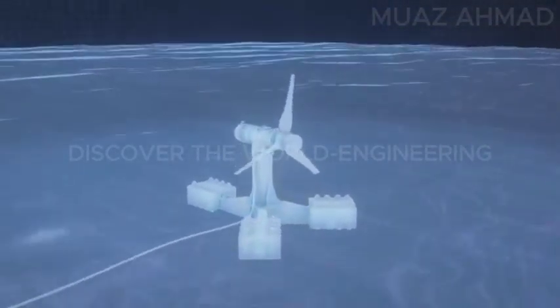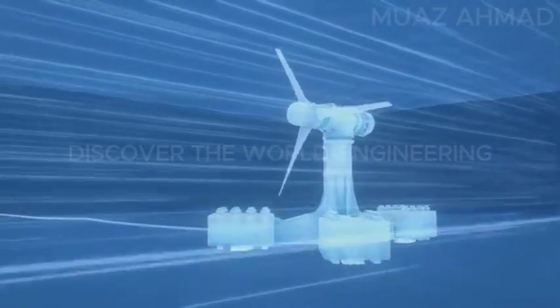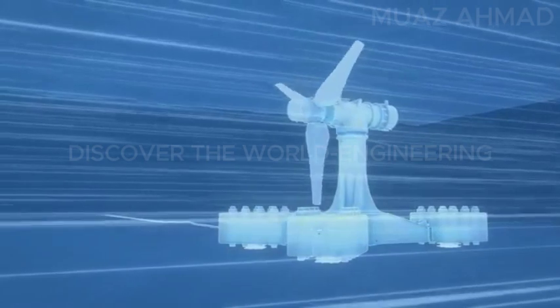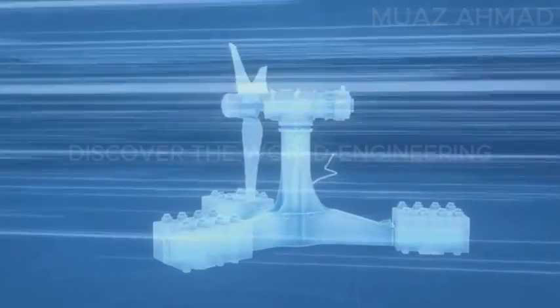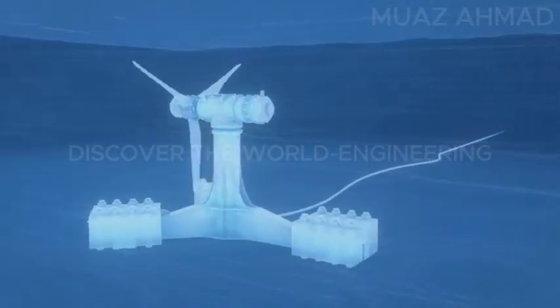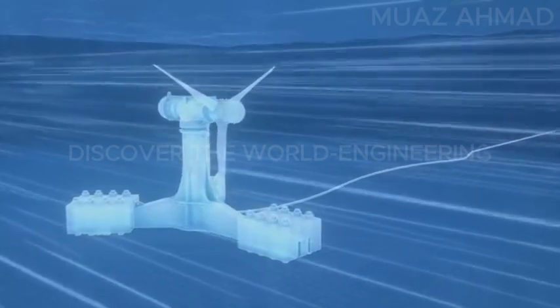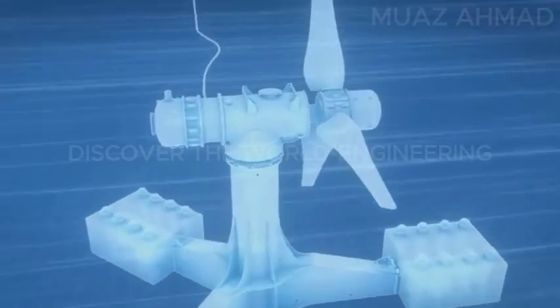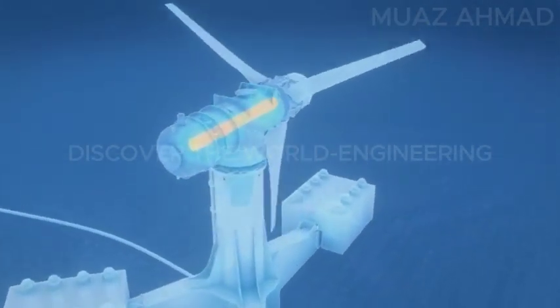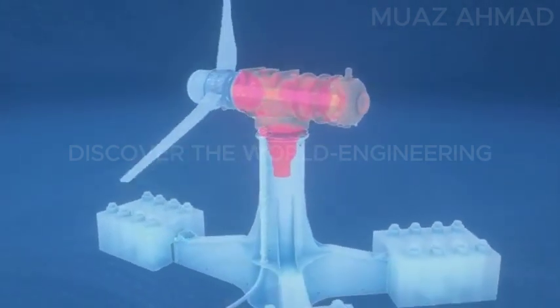But before disappearing beneath the waves, the turbine must first prove itself on land. Without its blades, the team connect the shaft to a test rig to simulate the extreme dynamic loads it will experience under the sea. Over the course of 6 weeks, the powerful test rig drives the shaft with the same force as it will experience under the full tidal flow. But as well as turning the shaft around, the test rig can apply hundreds of tons of force, pushing it back and bending it to the side, just like the turbulent ocean.